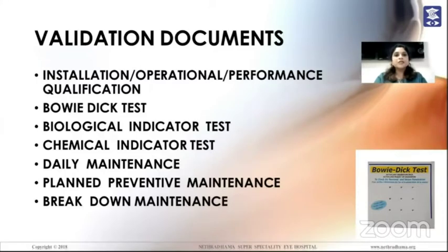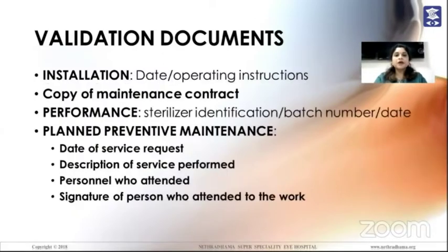The performance indicators can be biological indicators or chemical indicators, and this validation document should also have daily maintenance, planned preventive maintenance, and breakdown maintenance records. It should have the date, operating instructions of the equipment, and a copy of the maintenance contract. This can be maintained in the biomedical department, but it is always better to have one in the OT.